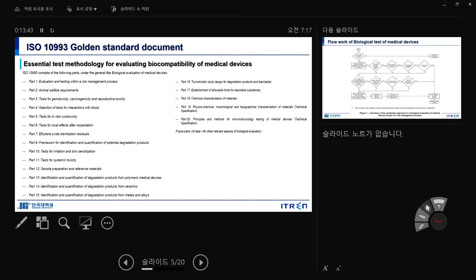Part 5: in vitro study basic concepts — test for in vitro cytotoxicity. Part 6: test for local effects after implantation, like subcutaneous study or skin study. Part 7: ethylene oxide sterilization residue — after gas sterilization, your material may have some residual toxicity from ethylene oxide. Part 9: framework for identification and quantification of potential degradation products — how you qualify and quantify degradation.